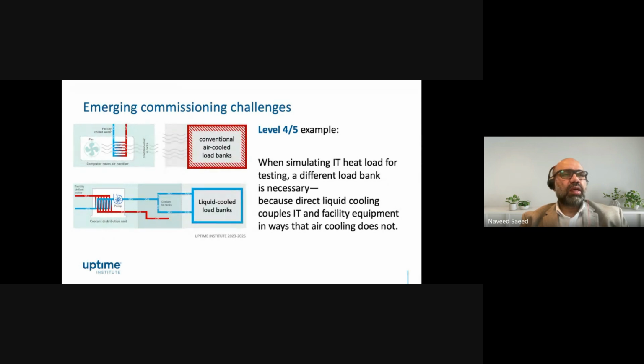But when we talk about direct liquid cooling, DLC or cold plate cooling, there's a lot of variation there. This variation can go up to 60-40%. For example, 60% of the heat will be rejected through the liquids, but 40% of the heat is still required to be rejected through the air. Which implies that for a 100 kilowatt rack, and I'm not talking about a 200 kilowatt or 500 kilowatt rack, I'm just talking about a 100 kilowatt rack, 60% means that 60 kilowatts will be rejected through the coolant liquid side, but the 40%, which is 40 kilowatts per rack, which is immense, which is still double that of traditional air-cooled systems, is required to be rejected by the air.